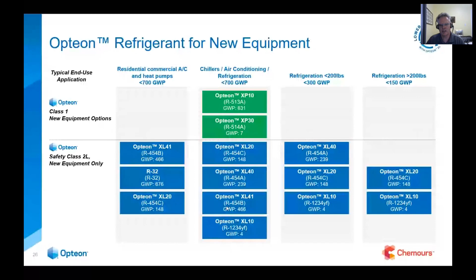And then when we get to the larger systems, where the requirement in the US regulations is less than 150, it really comes down to two. And we're primarily going to see, I think in this case, 454C. But you can see when we look at the 2Ls, there's really primarily 454A, 454B, and 454C that are going to become commonplace in air conditioning and refrigeration as we transition to lower GWPs and new equipment. So that's where we really look at it as 454A, B, and C, the ABCs of refrigeration.